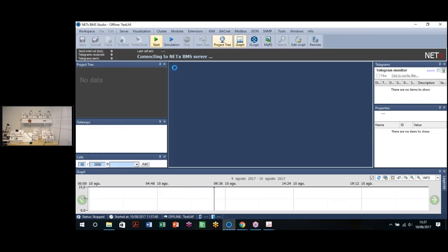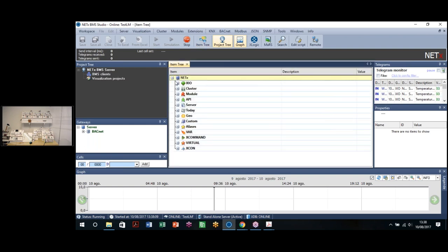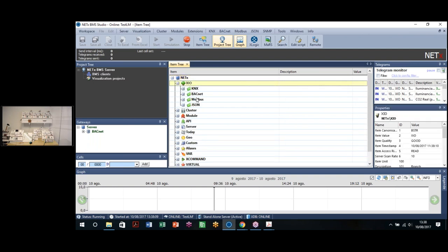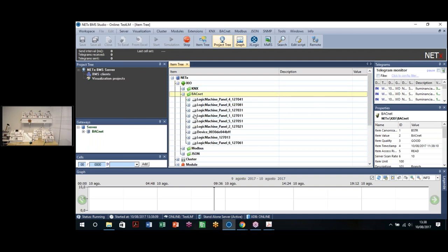We can exit, start the BMS, and you will see here, this is just a tool for recovering information, but you can create a SCADA, a central SCADA visualization with all this information. You can do energy management wherever you need. So in a different layer, if you have, for example, 200 stores wherever they are, worldwide, or a flat complex with 200 or 500 flats, it's very easy to integrate all the information in one central place where you can have KNX, BACnet, Modbus directly. In this case, we have integrated before in LogicMachines, and then we have all this information as BACnet. But you could have it directly or duplicated in KNX and BACnet for redundancy and so on.